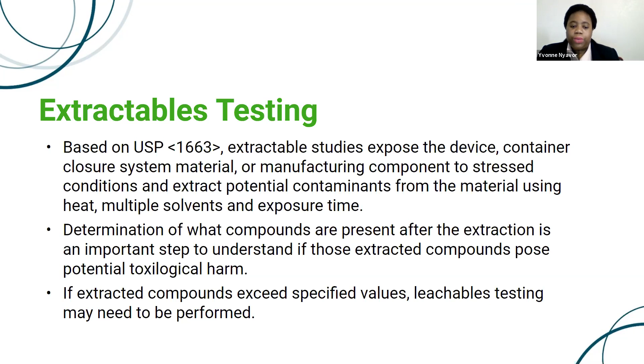And then for leachables or extractables, first of all, we use a method that is based on USP 1663. Extractable studies expose the device or its containment or enclosure system material or the manufacturing component. So in this case, we expose the device to stress conditions, and then we extract potential contaminants from the material. And we use heat or multiple solvents and exposure time to basically establish if there is any component of this device, or anything that is being extracted out of this device, that would require further testing. So we will typically go ahead and identify what compounds are present after an extraction is performed. And then we do this to understand if those extracted compounds would pose potential toxicological harm. So if any of these would, we would proceed with leachables testing.